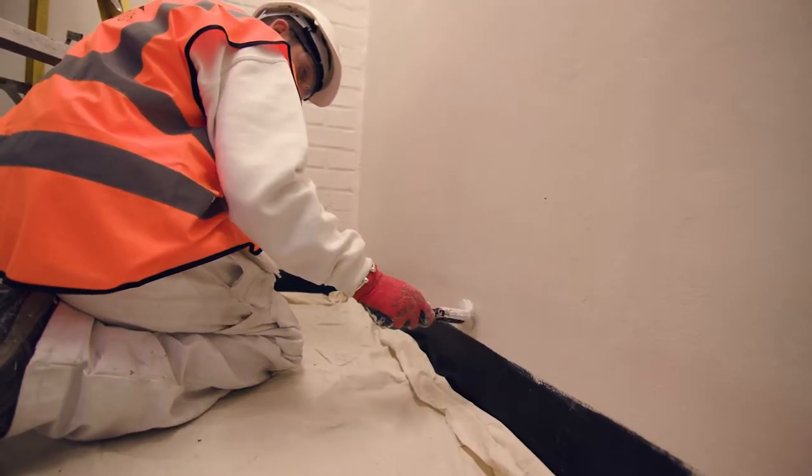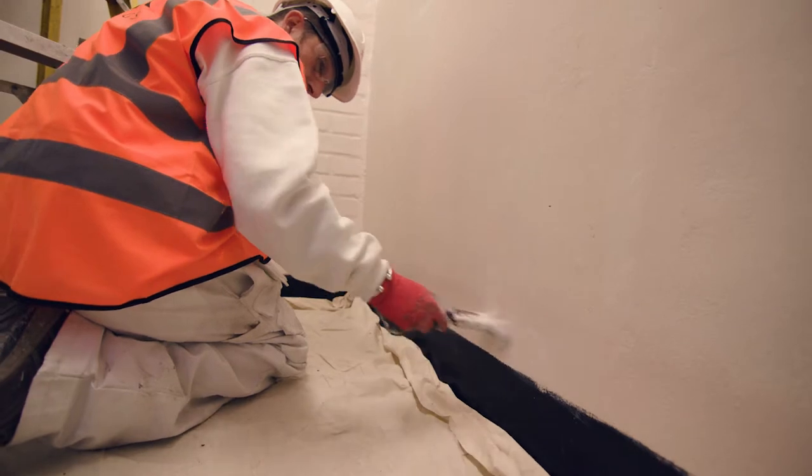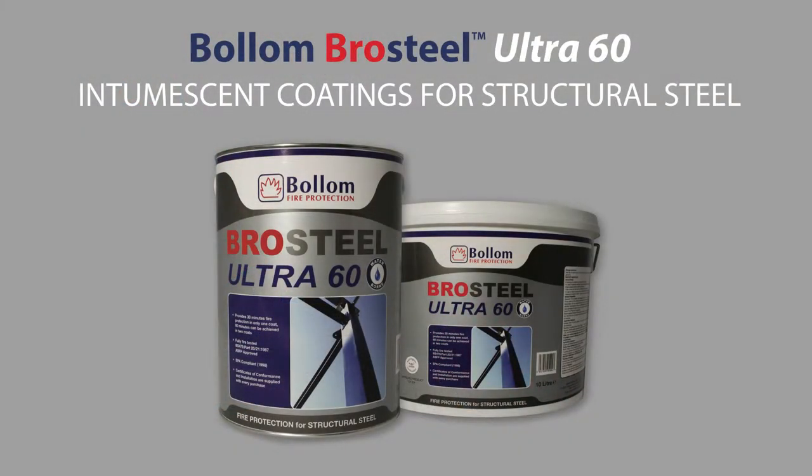At Bollom we offer intumescent coating solutions for all vulnerable areas of buildings. Brosteel Ultra 60 is a thin film water-based intumescent coating that provides up to 60 minutes fire resistance to structural steelwork. In the majority of cases, 30 minutes fire protection can be achieved with one coat and 60 minutes with two coats.